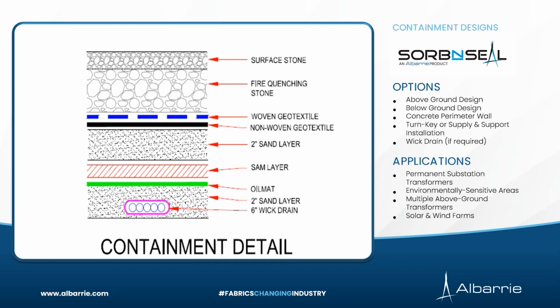The other effect is if you use crushed stone or very fine stones in areas subject to very cold temperatures and ice buildup, you can create an ice sheet over the top. Then if you had a spill, it might bypass the containment. So you want to make sure the surface stone is a clean washed stone, not a crushed stone, and well graded over the range. Again, it's close to 1.5 to 3 inches in size, or if smaller, pretty close to that size.